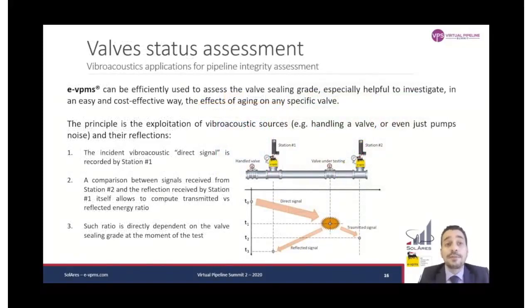Another topic is valve status assessment. For example, we are able to tell if a valve under testing is properly closing or not, or if it is leaking product. All this by analyzing the ratio between an energy source, which can be generated by handling a valve, and the transmitted and reflected signal.